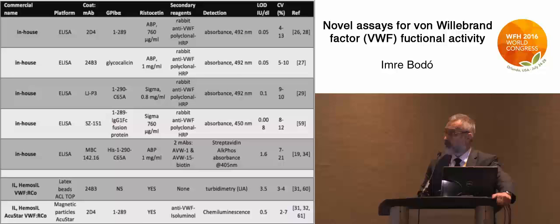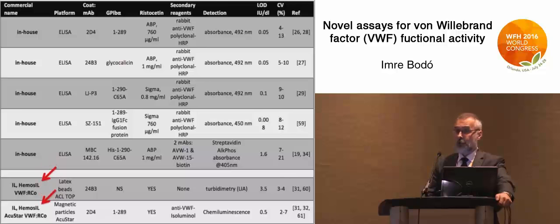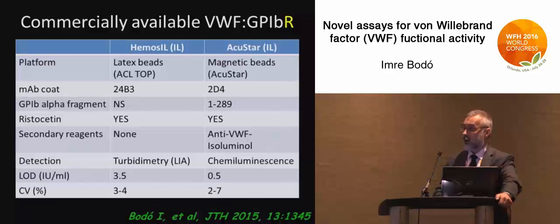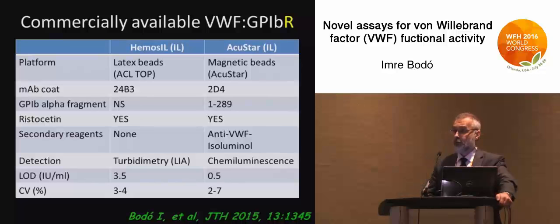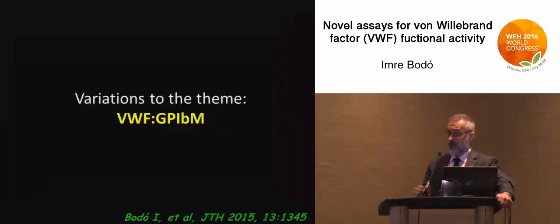Unfortunately, there is not one new assay but multiple versions. Each row on this busy slide represents a publication of one of these assays — those using ristocetin — and each column is an attribute that differs across them. Only two are commercially available, both marketed by IL: one for the ACL Top platform and the other for the ACL AcuStar. They use different coats to capture von Willebrand factor; both use ristocetin, but the concentration is not disclosed. These assays now show a spectacular limit of detection — they are very sensitive. The AcuStar goes below 1%, which was absolutely unheard of in the old days.